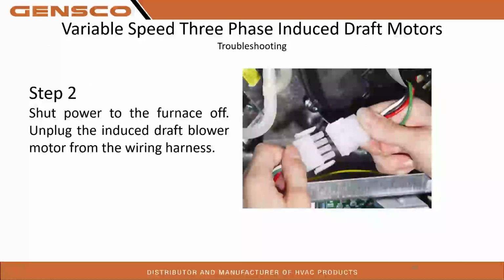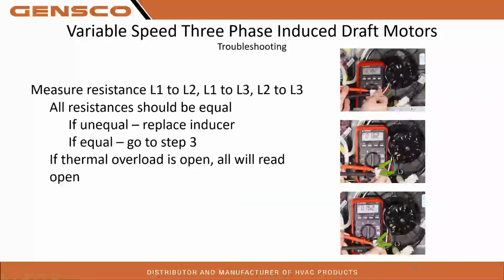So how are you going to troubleshoot it, knowing we don't have voltages we can run on? Obviously we're going to shut the power off to the furnace. We're going to unplug the induced draft blower motor from the wiring harness, so we're going to disconnect it and make the motor stand alone completely. And then we're going to measure the resistance, like a 3-phase motor, right? So L1 to L2, L1 to L3, and L2 to L3. We should have equal resistances, right? If unequal, we're going to replace that inducer motor.